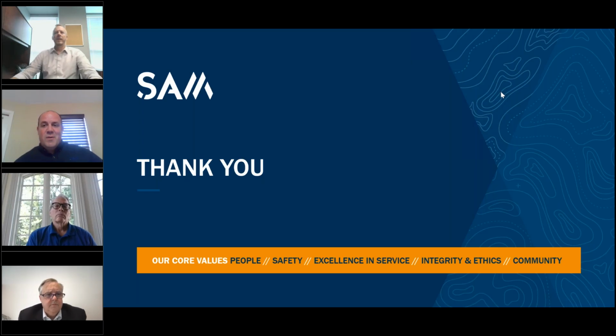I wish I could tell you it's between 70 and 90, but it's between 1 and hundreds each and every time. We often find the most verifications are required on older substations that don't have good as-built documentation. Also, for utilities that have grown over the years by purchasing electric co-ops or smaller utilities, they'll have substation documentation from the original owner from many years ago, and the large utility now owns that asset and has to make sure it's part of their FAC compliance record keeping. At those substations, you often need a lot of measurements to get a complete idea of your facility rating. That's where I see the most need for measurements.